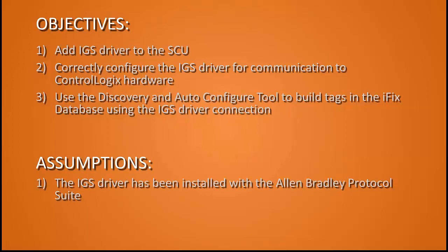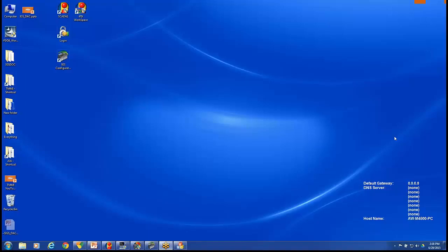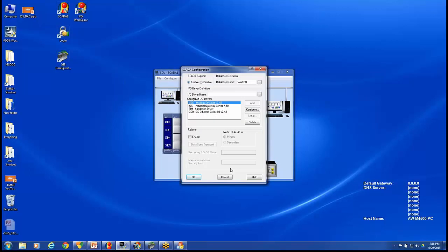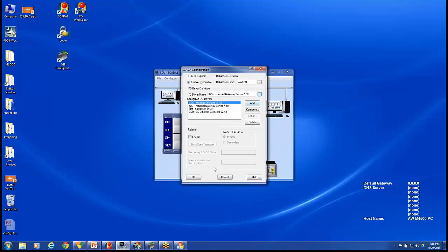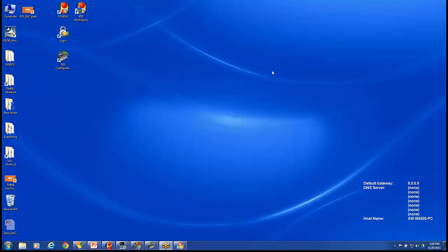Our assumptions are that the IGS driver has already been installed with the Allen-Bradley protocol suite selected, and Ethernet connectivity to the controller has been established. We'll start by going into our system configuration utility and making sure the IGS driver is listed. That's done under the SCADA configuration. If your IO driver is not listed, choose your IO driver name from the list and click Add. Once that change has been made, a restart to the iFix system must be done.